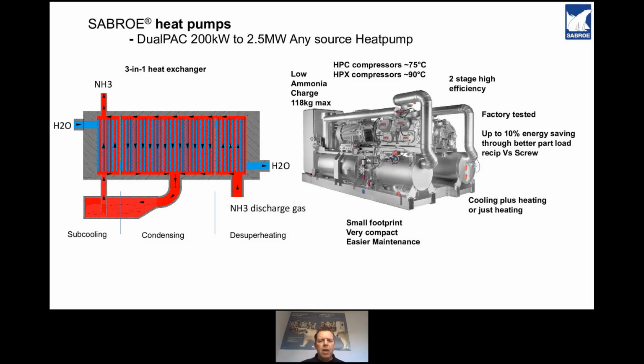Press the next button. So how does it work? Now, just basically the slide on the left here, just to show you roughly what it is. This is a shell and plate heat exchanger. So your district heating water would enter at the top left at 40 degrees. It passes through 3 chambers. It passes through the plates in the subcooling section, the condensing section, the desuperheating section, and finally, having picked up, let's say it went in at 40, coming out at 70, and back into your heating system. And using contraflow, the discharge gas will enter in the opposite corner and travel right to left, obviously losing heat and giving that heat to the water.